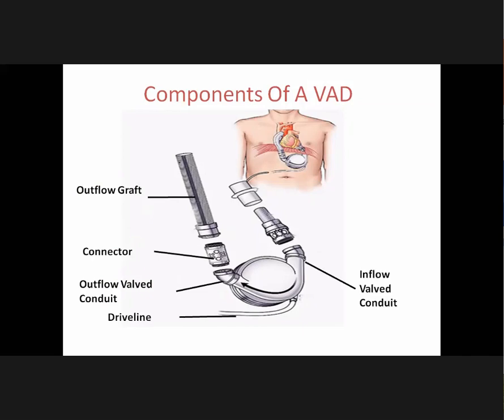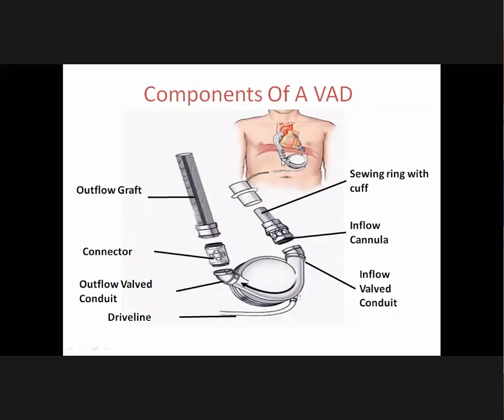Components of a VAD include: outflow graft, connector, outflow valve conduit, driveline, inflow valve conduit, inflow cannula, and sewing ring with cuff. Blood from the heart flows through the sewing ring with cuff into the inflow cannula, continues forward through the conduit, and is driven out through the outflow valve conduit via a connector to the outflow graft, which is connected to the ascending or descending aorta.